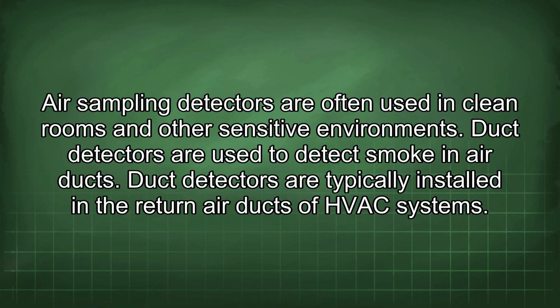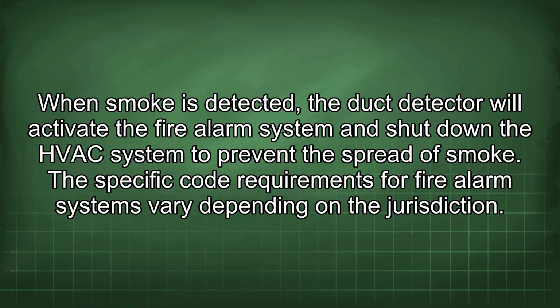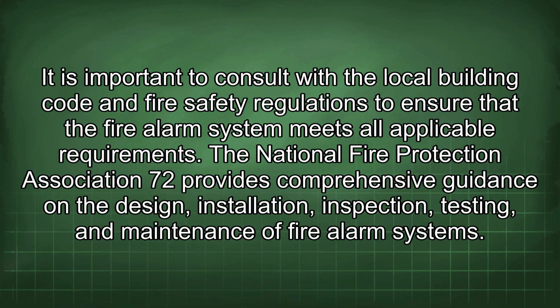Duct detectors are used to detect smoke in air ducts. Duct detectors are typically installed in the return air ducts of HVAC systems. When smoke is detected, the duct detector will activate the fire alarm system and shut down the HVAC system to prevent the spread of smoke. The specific code requirements for fire alarm systems vary depending on the jurisdiction. It is important to consult with the local building code and fire safety regulations to ensure that the fire alarm system meets all applicable requirements.